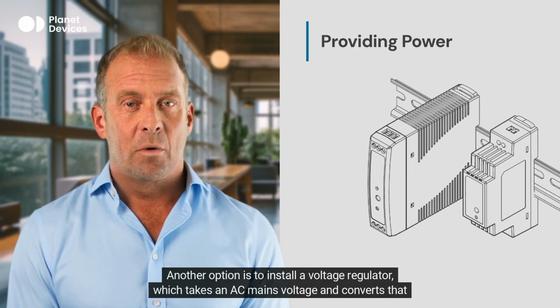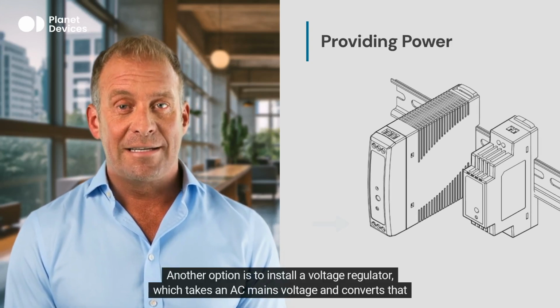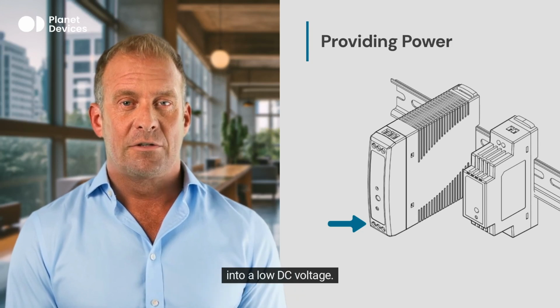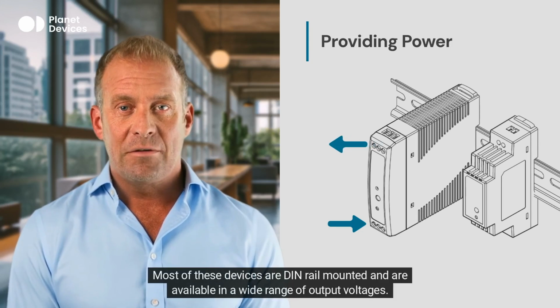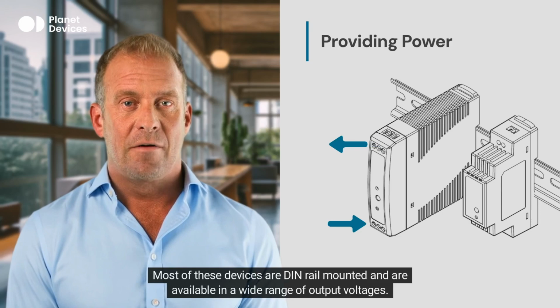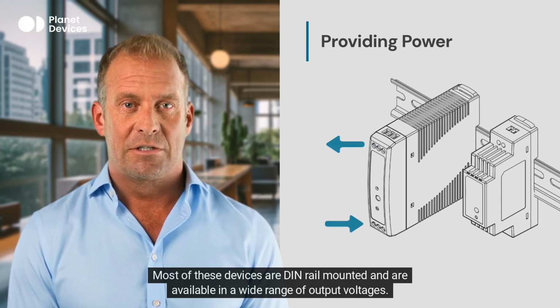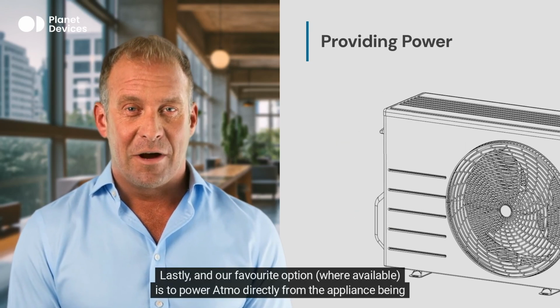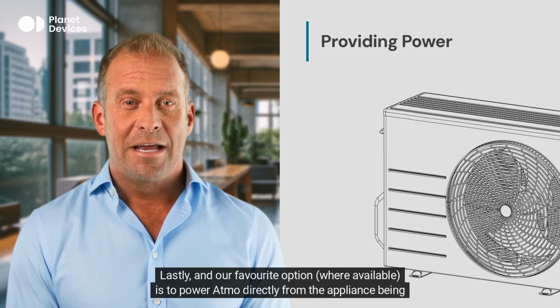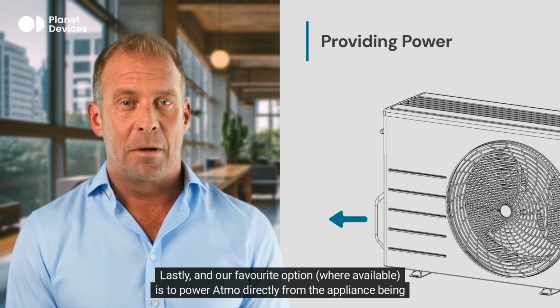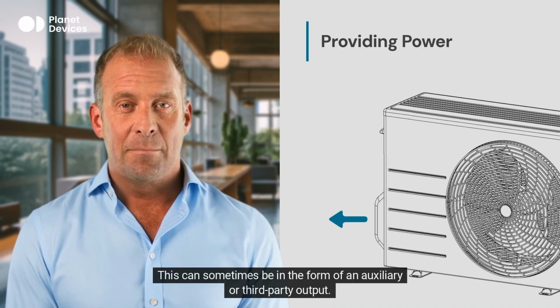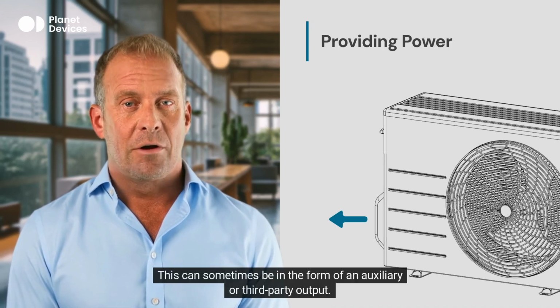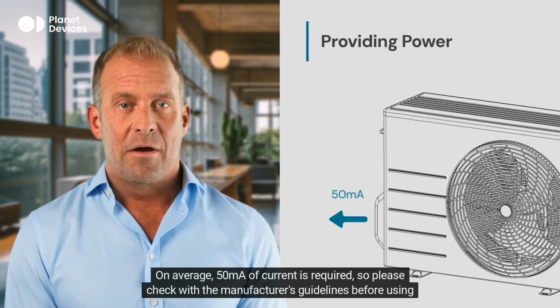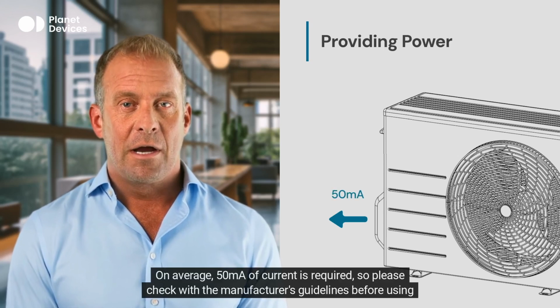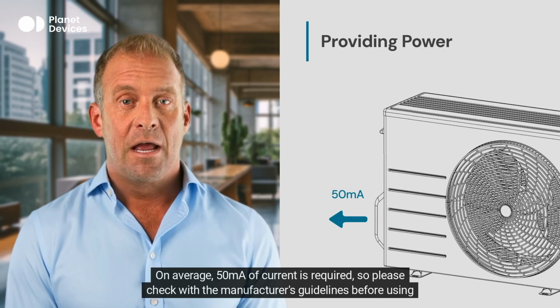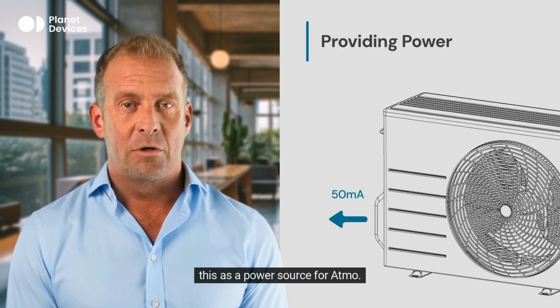Another option is to install a voltage regulator, which takes an AC mains voltage and converts that into a low DC voltage. Most of these devices are DIN rail mounted and are available in a wide range of output voltages. Lastly, and our favorite option, where available, is to power Atmo directly from the appliance being installed. This can sometimes be in the form of an auxiliary or third-party output. On average, 50 milliamps of current is required, so please check with the manufacturer's guidelines before using this as a power source for Atmo.